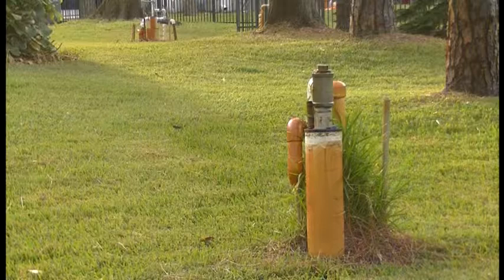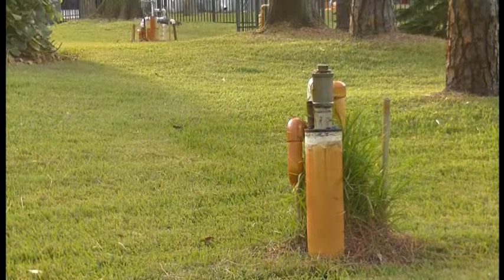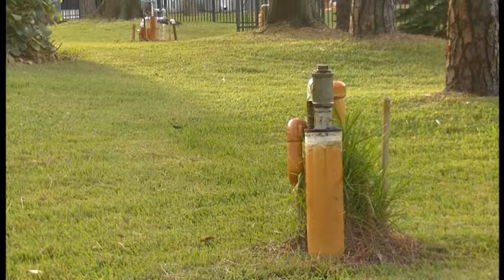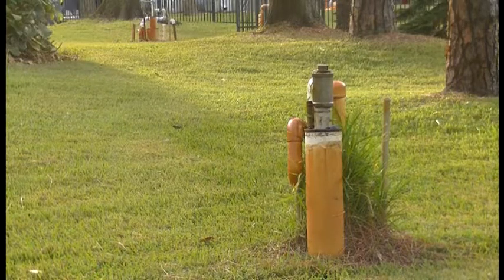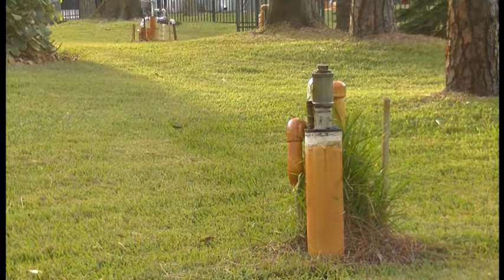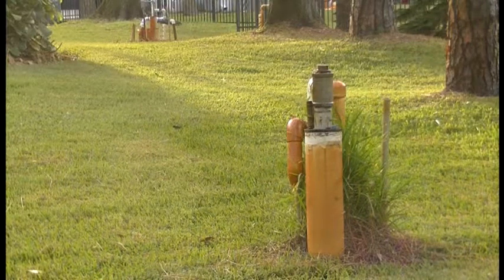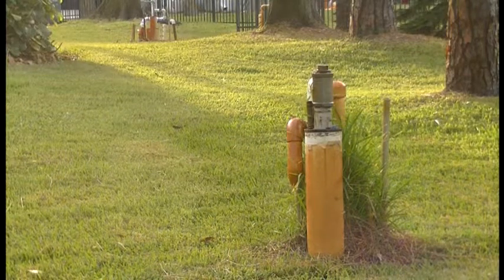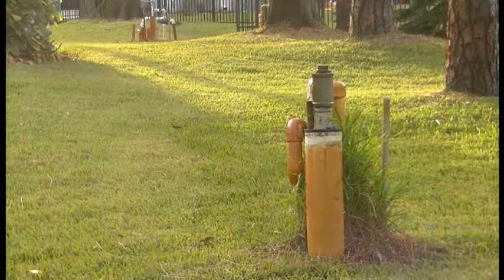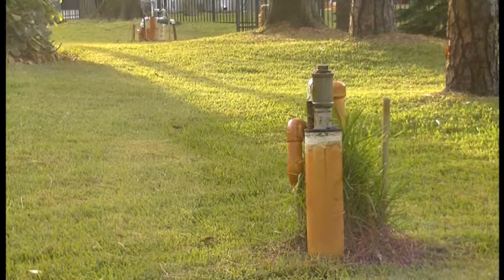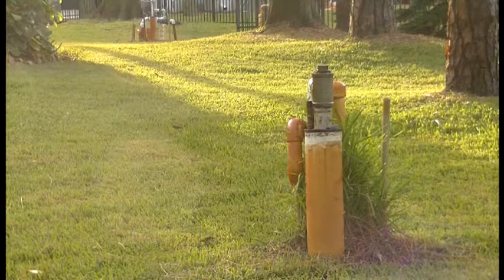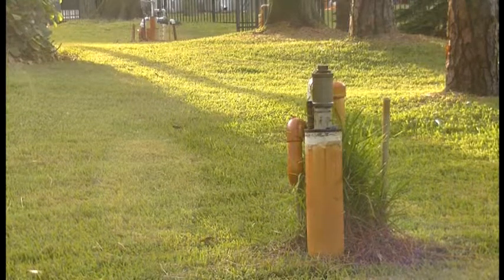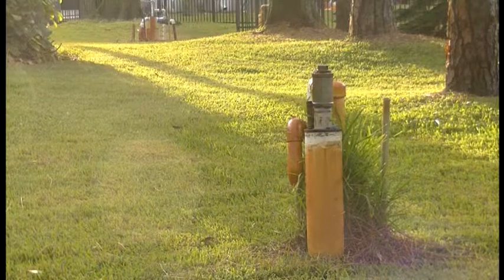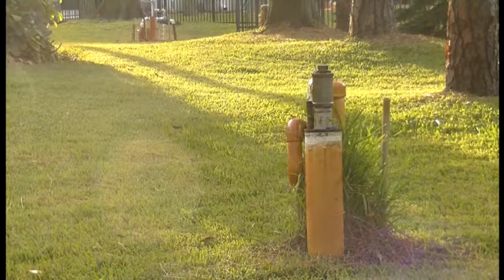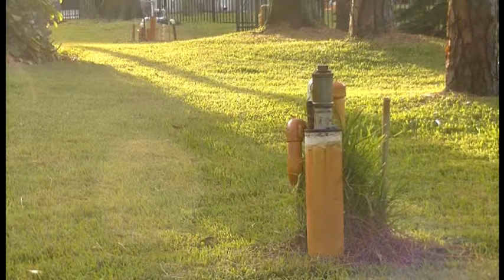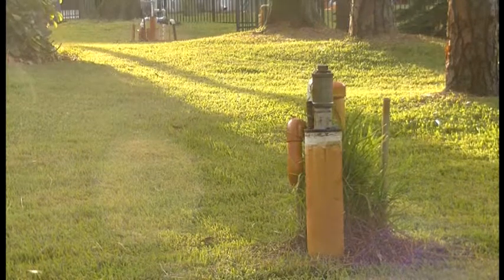So basically this system pumps water out of that distant well, runs through some piping through the ground over to the house, through the geothermal heat pump equipment in the house, is returned down, back out of the house, through the ground, and back into this well that you're looking at right in front of you. This pump receiving well here, injection well, is set at a 40-foot drop tube of 2-inch diameter, and basically the system runs at a 40 psi pressure, and the injection well has about 12 psi pushing water back into the well, and that's all a function of the drops through the system and the setting.